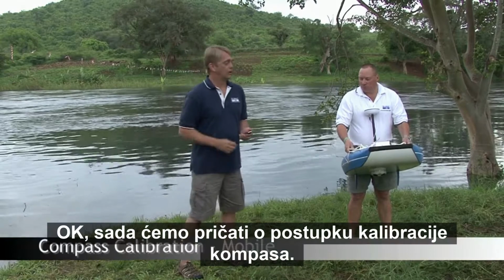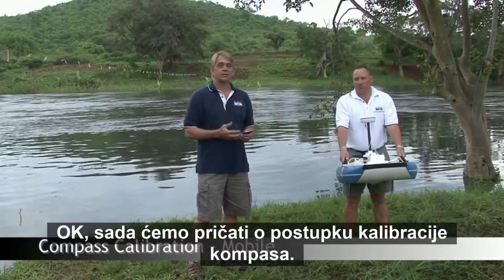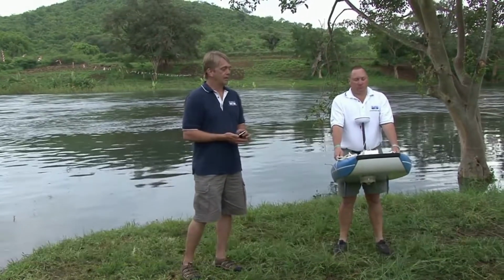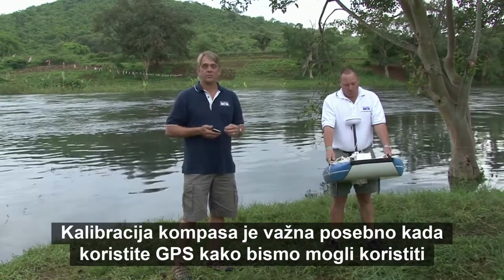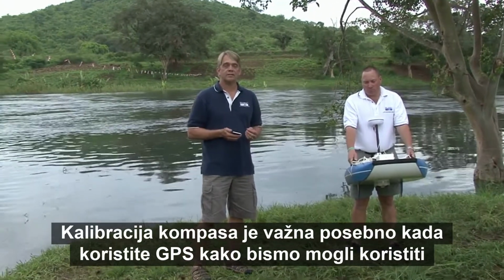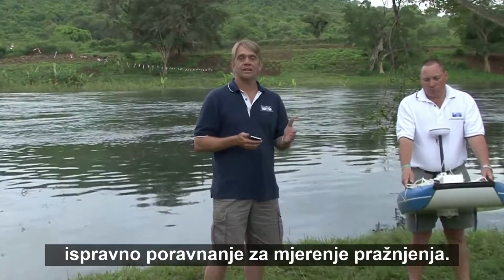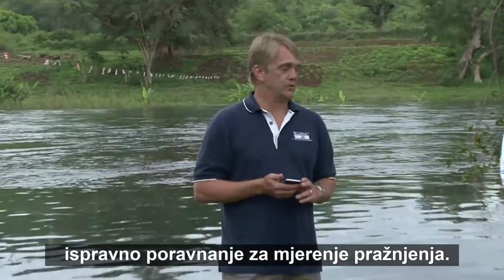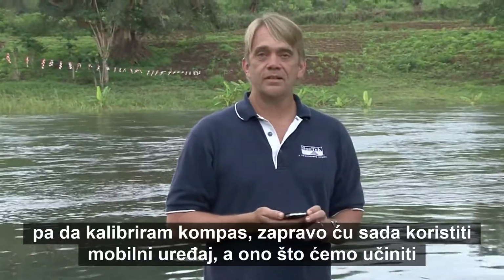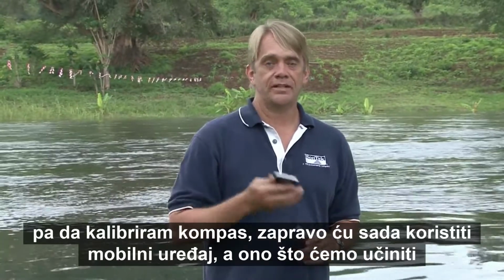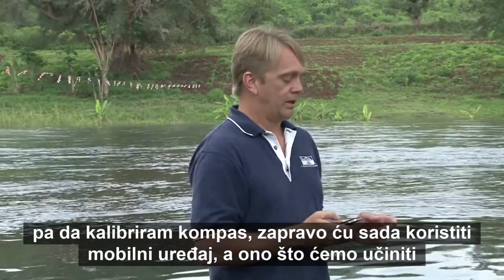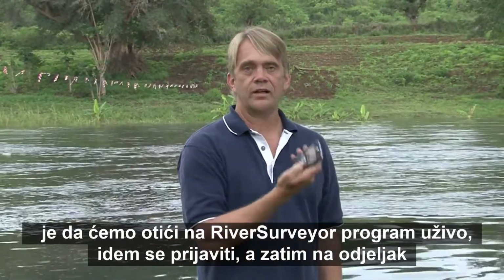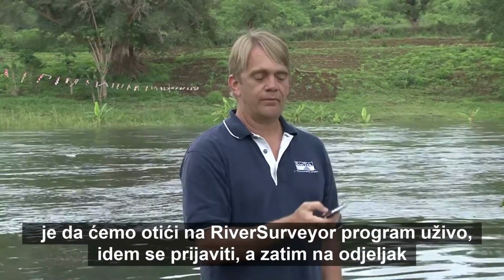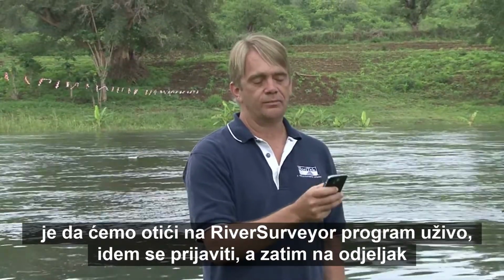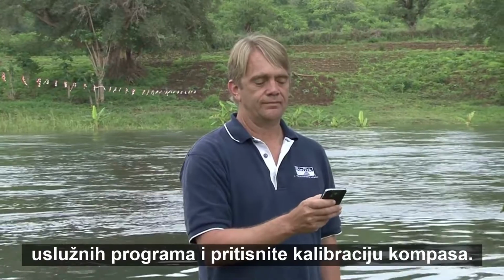Okay, now we're going to talk about actually the procedure to calibrate the compass. A compass calibration is important, particularly when you're using GPS, so we can use the correct alignment for the discharge measurement. So to calibrate the compass, I'm actually going to use the mobile device right now. And what we're going to do is go to the RiverSurveyor Live program, go to the Utilities section and press Compass Calibration.